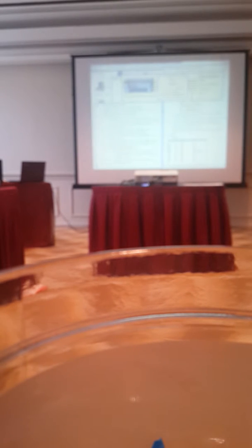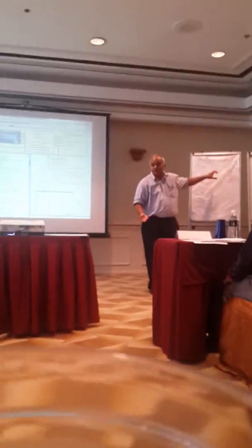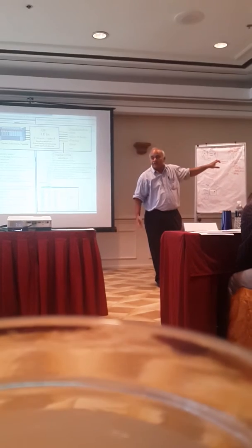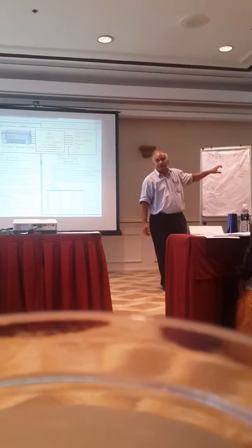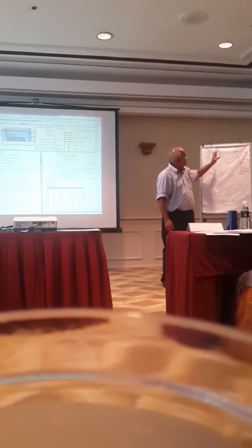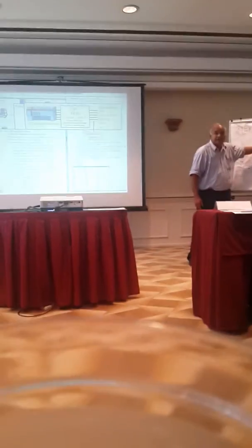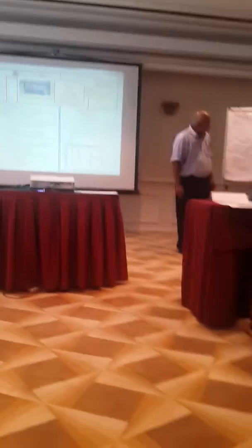What we want to do now is OPC. Now, what is OPC? Remember, I told you there are two ways that your controller can communicate with your BMS. One is using Modbus - Modbus is a driver - or using BACnet, or LonWorks. Another way is for the controller to communicate directly with the SCADA software, with the BMS software. Now, how does it work?